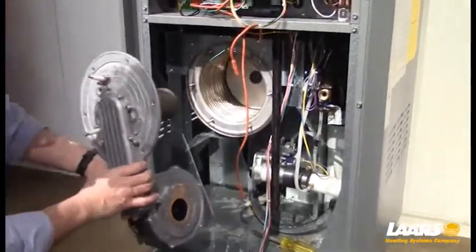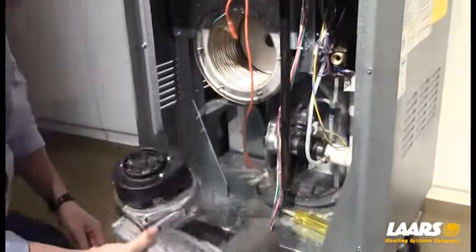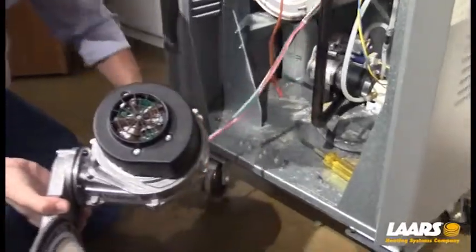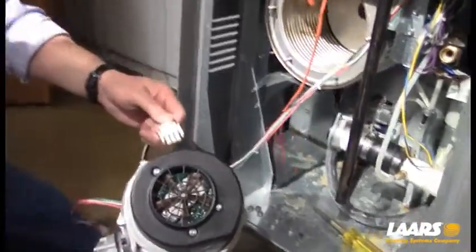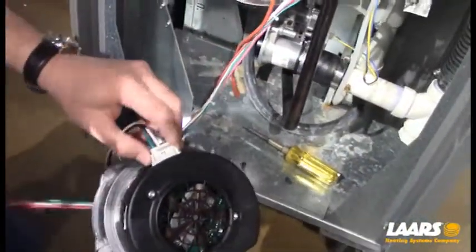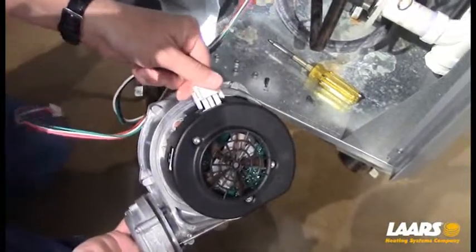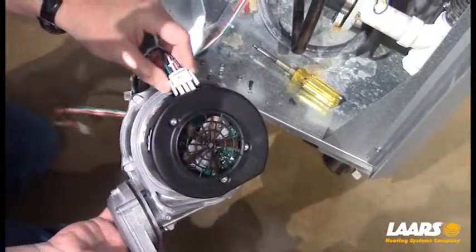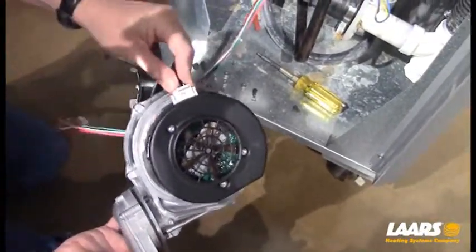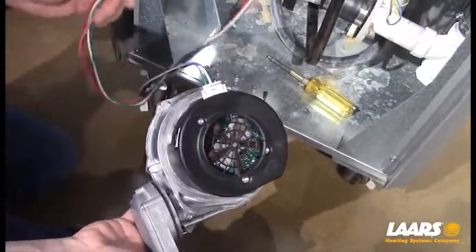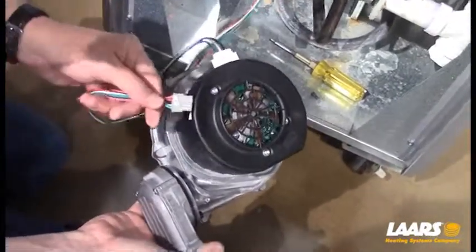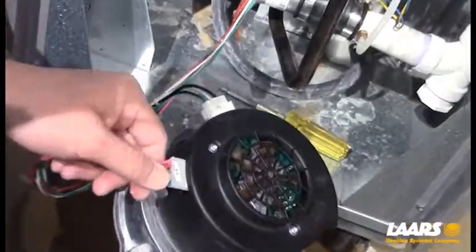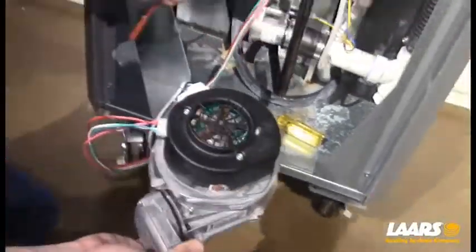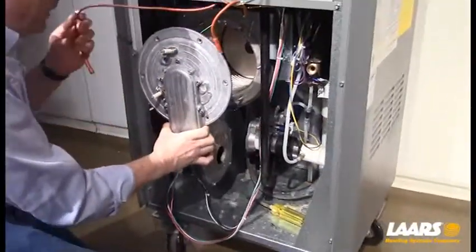So prior to putting the burner head back into position, it's easier if you can remember to wire the blower back to position. Okay, it can only go in one way. If you try and put it in the wrong way, it will not line up. Okay, so we have line voltage, and we have a low voltage DC signal that drives the blower and fan speed. Okay, so next we're going to slide this right into position.